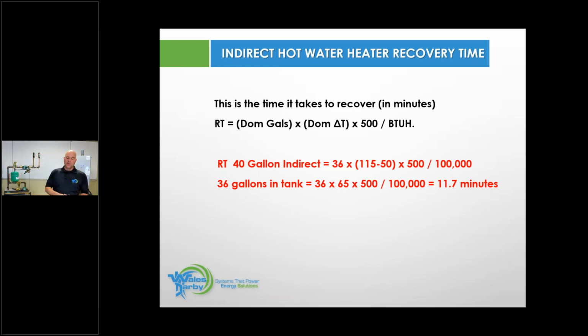So because we don't see that often, we want to give you guys another formula. So when you get questioned by the homeowner, hey, I get 2 showers out of this 40-gallon indirect, why? I want to answer the whys. So in this formula, RT, that's recovery time, equals domestic gallons, so that's the indirect, times domestic delta T times 500. There's that 500 again. And then we're going to divide that by the BTU of the boiler that's tied to the indirect. So what does this look like?